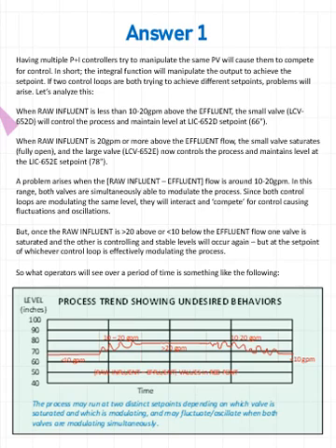and at some point it might reach the higher set point of 78 once, if it gets up to 20 gallons and the LIC 652E takes over, or it might actually oscillate and then drop back down. It all just depends on that mismatch. So the mismatch kind of drives the behavior.